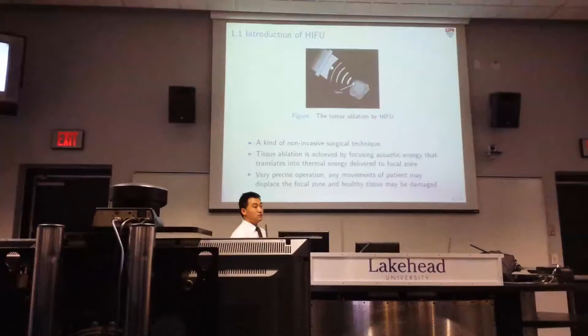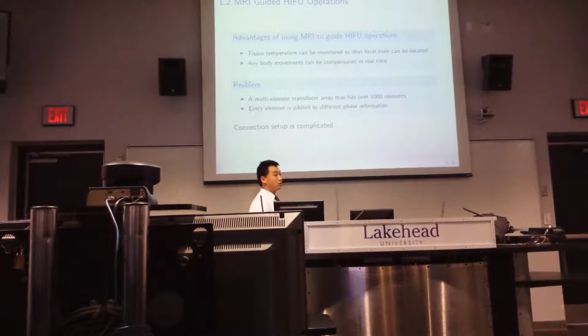Focused ultrasound is a kind of non-invasive surgical operation. And the tissue ablation is achieved by delivering the acoustic energy to a focus zone and translating it into thermal energy. This is a very precise operation. Any movements of the patient's body will displace the focus zone and cause healthy tissue damage. So to avoid that kind of damage, we are going to use the MRI to guide the HIFU.